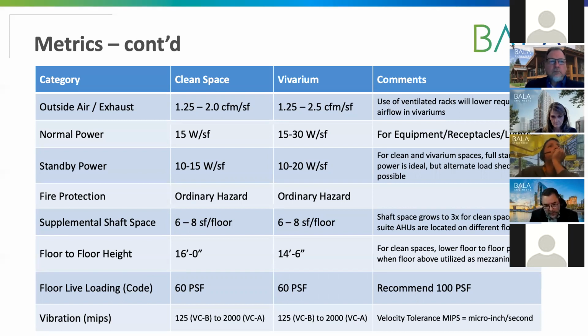Essentially what that allows us to do is to provide the desired air change rate ventilation, but it's predicated upon just the internal volume of the individual racks as opposed to the entire room volume. So a typical room might need about 15 air changes of airflow. If you utilize ventilated racks, you could drop that down to about 6. So you can see it's almost a threefold decrease. It does pay to have that discussion with your client, your typical lab user, to understand what their real needs are, because that can help formulate how you put these designs together.